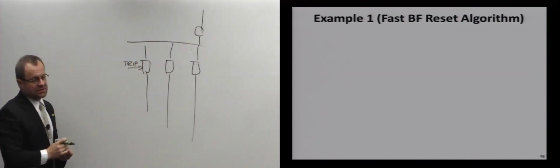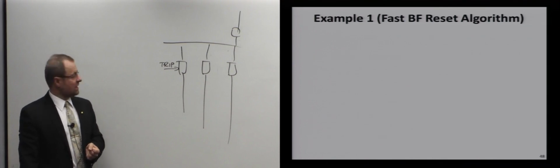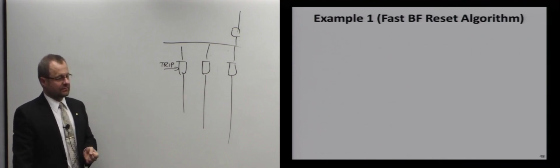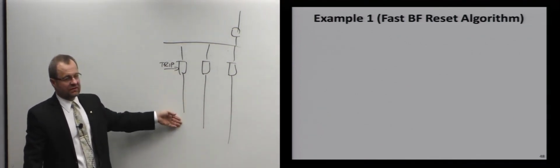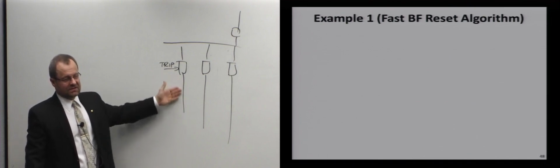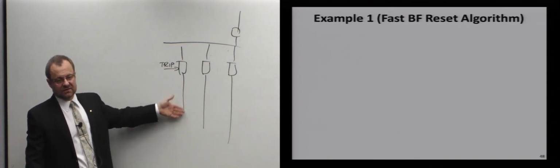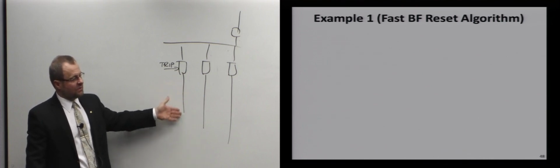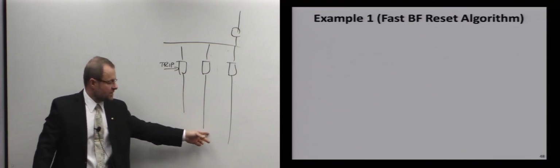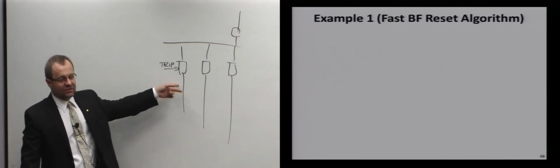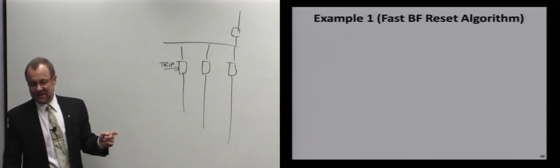and assume that you order this breaker to trip, right? If this is a misoperation, what harm did we do? We just tripped that circuit. Maybe it's a feeder to a subdivision, maybe it's a small city, maybe nothing will happen because that city gets power through this line. We will reclose, nobody will notice, right?